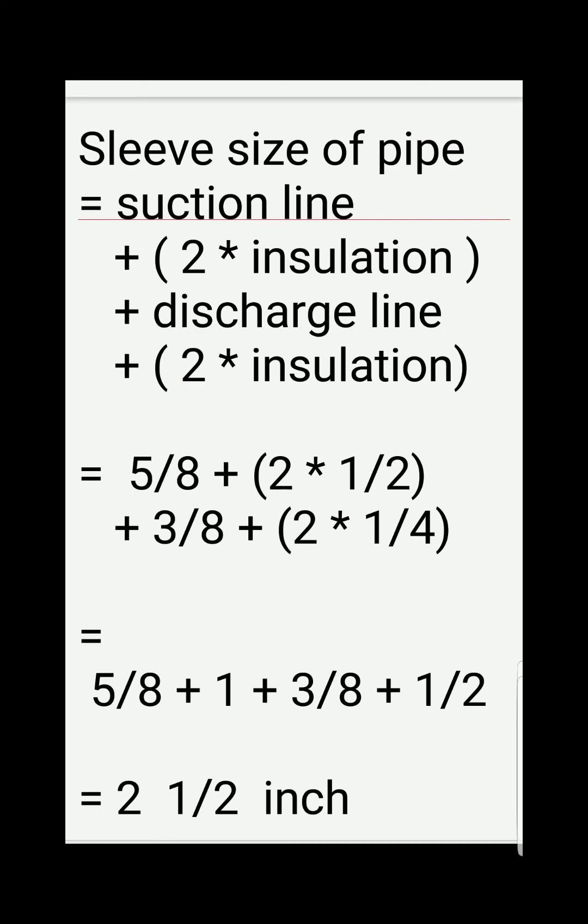Going back to the solution, so now we have 5/8 suction line plus 2 times 1/2 inch suction line insulation, plus 3/8 discharge line, plus 2 times 1/4 inch insulation of discharge line. So we add all those numbers and we find 2 and 1/2 inch in total. So that is the minimum size of the sleeve pipe.